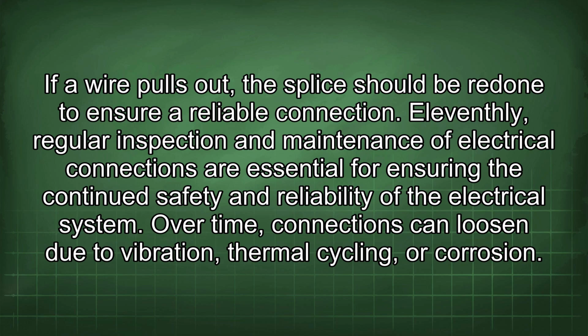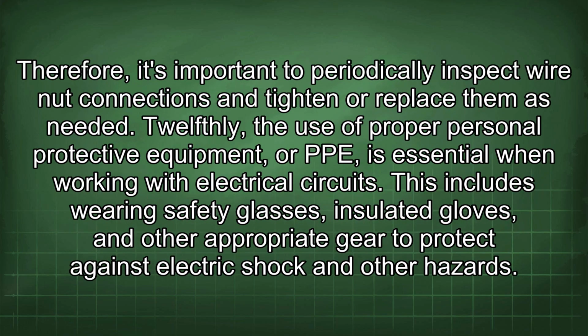11thly, regular inspection and maintenance of electrical connections are essential for ensuring the continued safety and reliability of the electrical system. Over time, connections can loosen due to vibration, thermal cycling, or corrosion. Therefore, it's important to periodically inspect wire nut connections and tighten or replace them as needed.